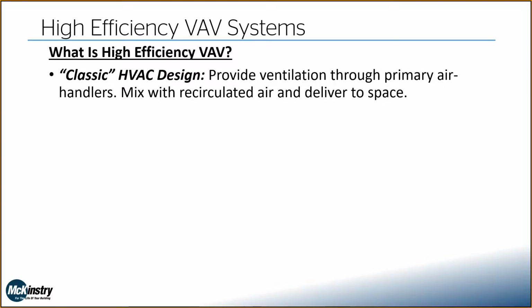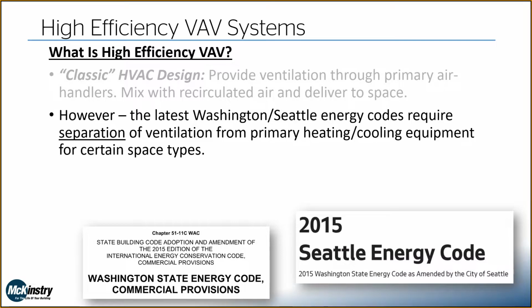So, what is it? In terms of what I'm calling classic HVAC design, what we've done for years and years is we typically will provide the ventilation air through our primary air handlers, mix that with our return air, and then heat or cool it, and then send it out to the space. But the latest Washington and Seattle energy codes are requiring a separation of the ventilation air from the primary heating and cooling equipment. These two systems need to be completely isolated from one another.